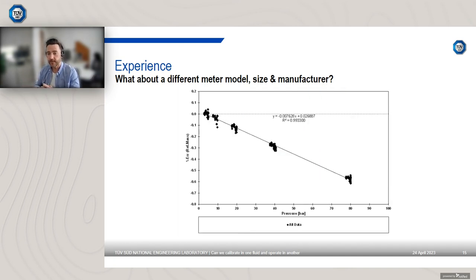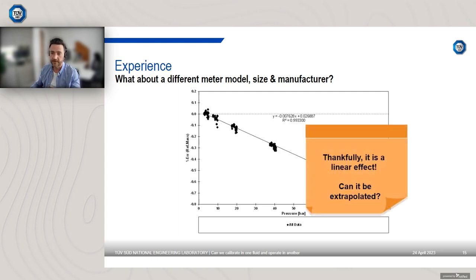So here we go, this is a different device. And for the previous charts I was showing you mass flow rate on the x-axis. On the x-axis here we have pressure. So this is the reference pressure in bar. On the y-axis we still have that deviation, so percentage error of the reference mass. And this is all the data. So I'm showing all the data together. So you can see the data at 5 bar, 10 bar, 20 bar, 40 bar and 80 bar. And you can see that the effect is clearly linear. And that's a good thing. It's a linear effect. So thankfully it's linear, because linear means easily correctable. You can see what we have here. You can see I've put the correction overlapped.